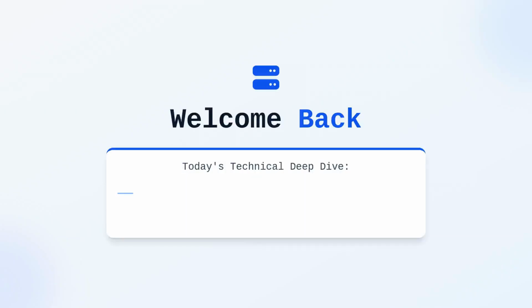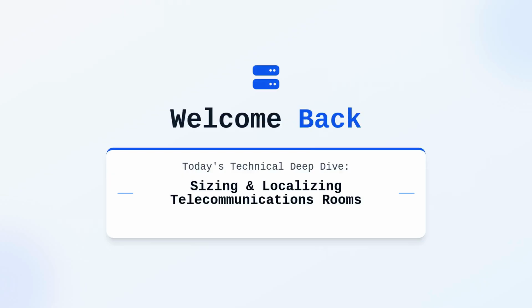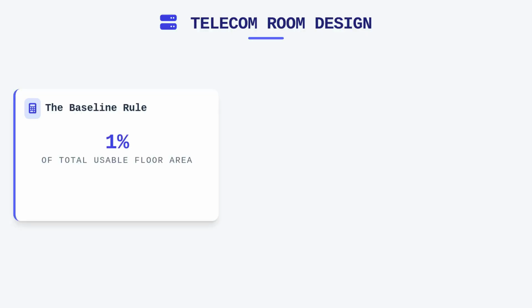Welcome back. Today we examine the technical requirements for sizing and localizing telecommunications rooms within modern commercial facilities. Designing a telecommunications room is an exercise in constraint management, where mathematical precision meets physical reality. The foundational rule of thumb mandates that a telecommunications room should occupy approximately 1 percent of the total usable floor area it serves. While this serves as a solid starting point for conceptual design, you must ensure that your calculations account for specific variables like equipment density and projected future growth.